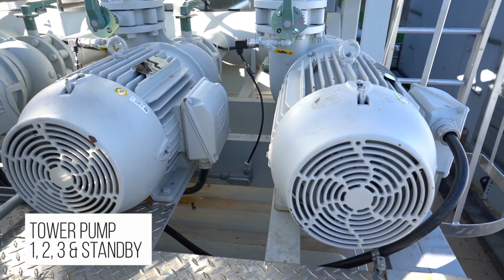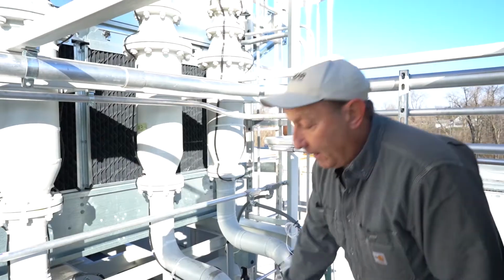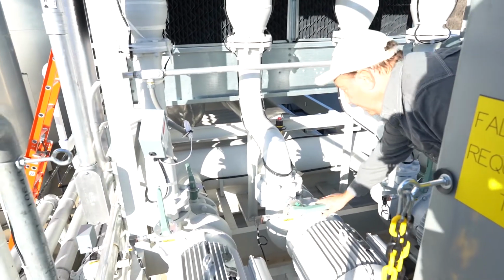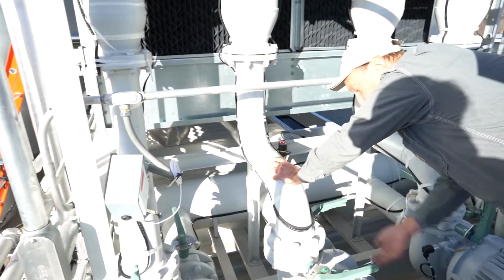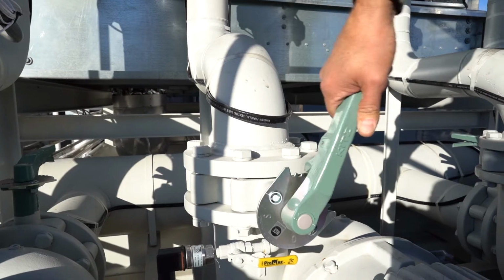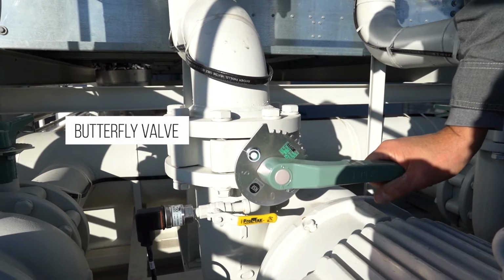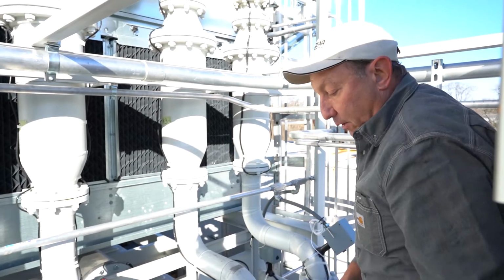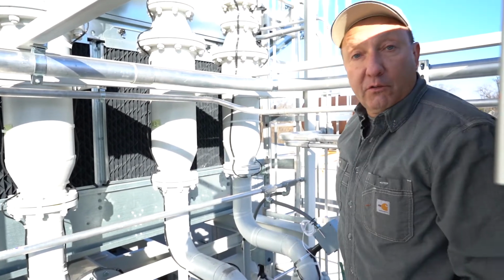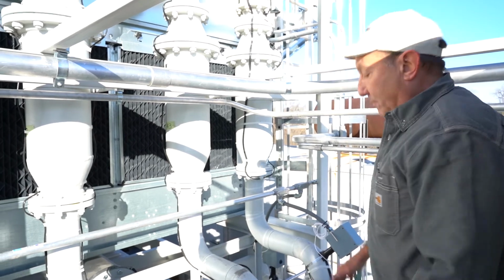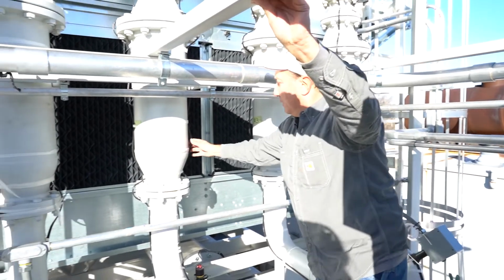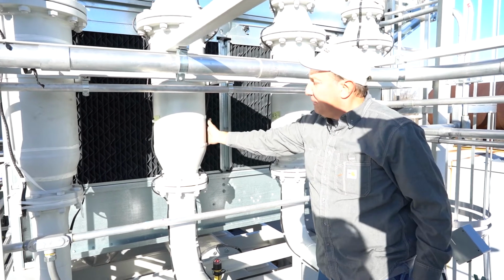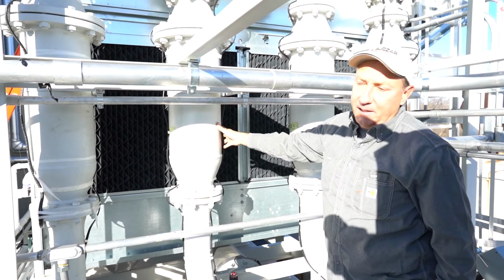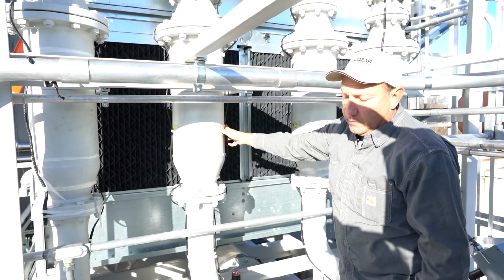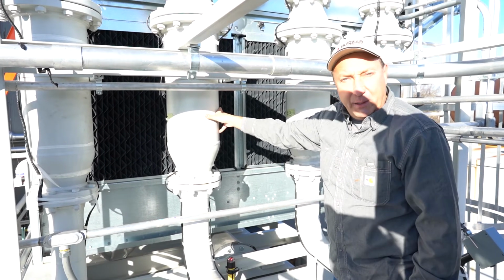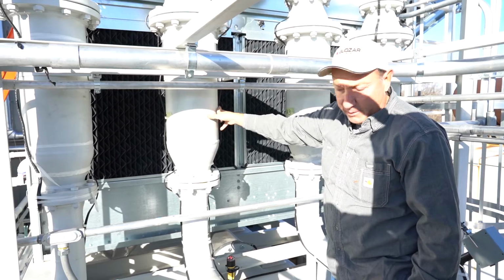In case one system goes down, it can be totally isolated by manipulating these butterfly valves here, and the pump can be isolated. You just simply lock out the 3-phase power, and you can drain the system right here and work on one pump while the system continues to run without any downtime. If you look here, all the piping is protected by heat trace. The heat trace is enabled, but the installation is incomplete at the time. This is all in the works. It's a construction site still for another week or so before we turn this over to the customer for production.